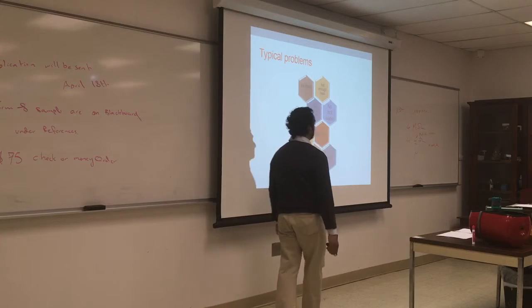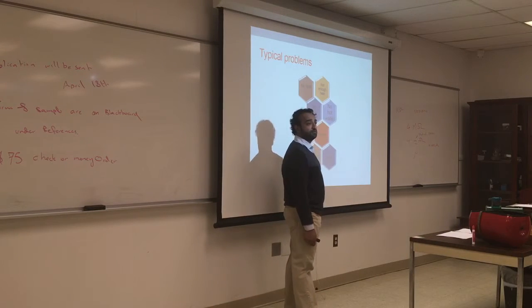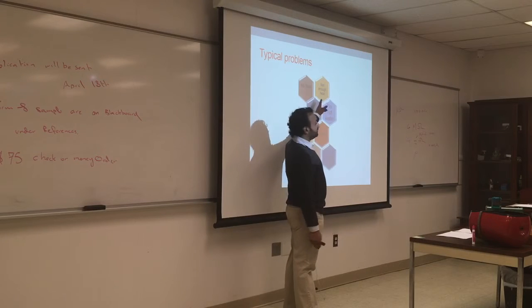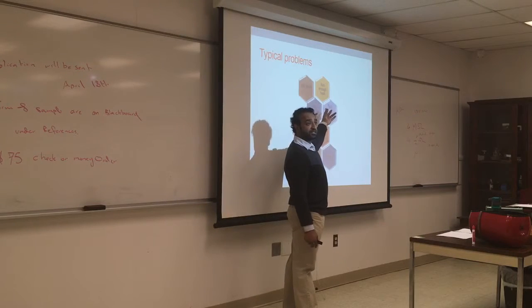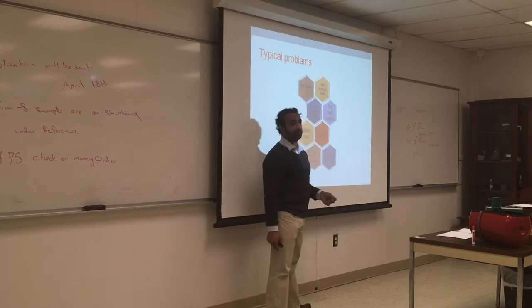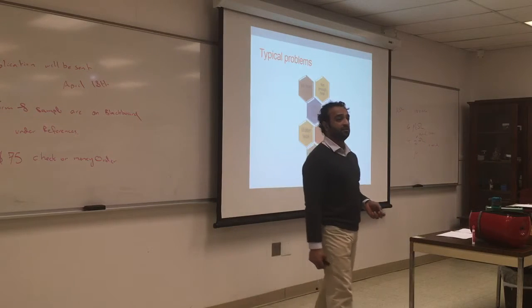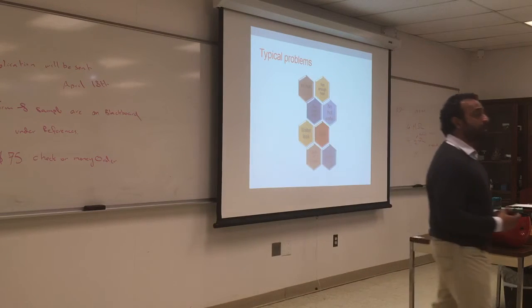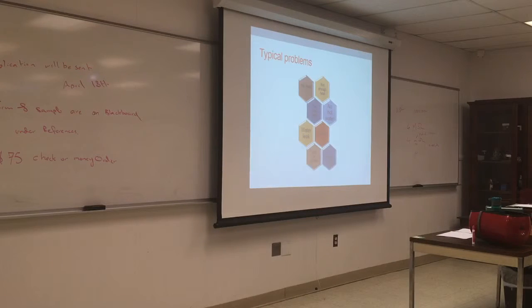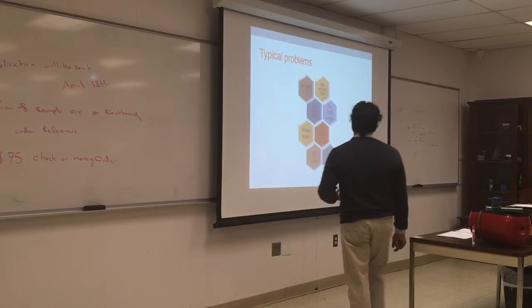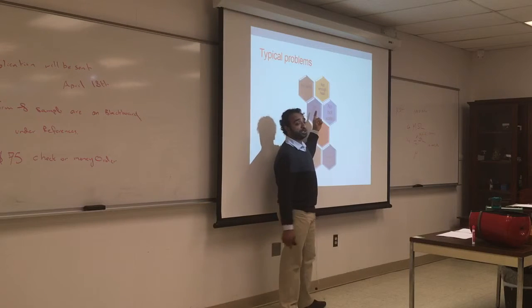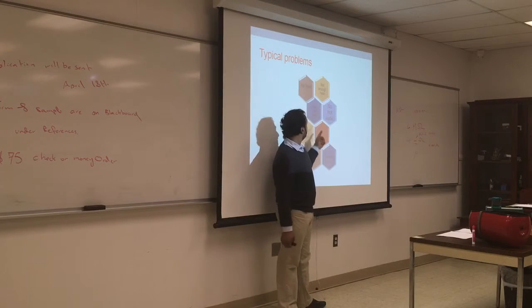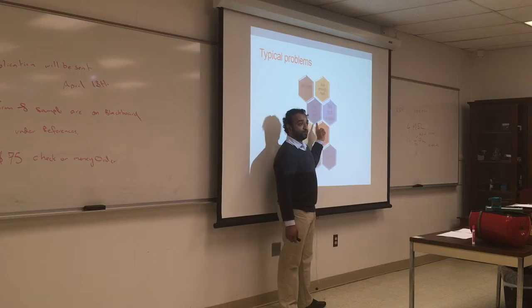No heat: the system is not working at all. There's no heat, there's no circulation. Not enough heat: the system is running, there's heat, but it's not enough. Something has been changed. It could be the water temperature in the aquastat. It could be the aquastat setting. It could be a thermostat issue. So if there is heat but not enough heat, you've got to check what's happening. It could also be that the system is so dirty that the heat exchanger is not absorbing enough heat. Too much heat: thermostat issue.